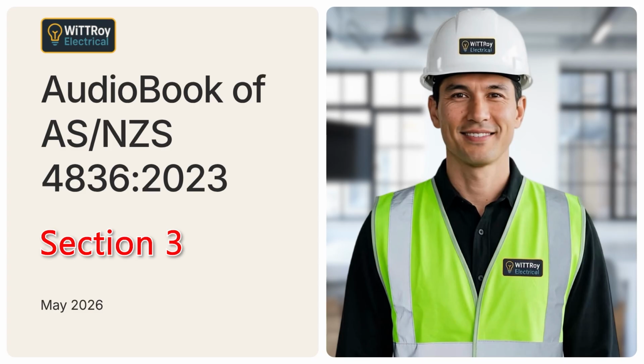Clause 3.1.4. Isolation securing devices and identification. Clause 3.1.4 explains how isolation must be secured and identified. After the isolating device is opened, it must be secured in the open position or in a zero-energy state. The purpose is to prevent accidental operation. No person must operate an isolator or use equipment while an isolation securing device is attached.